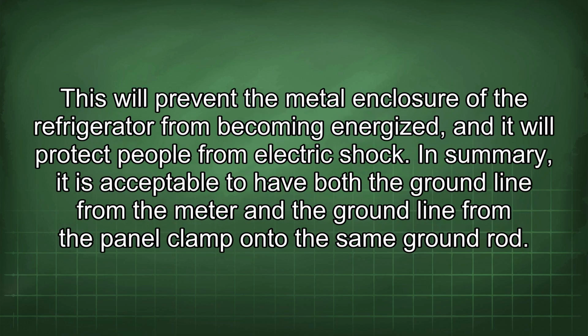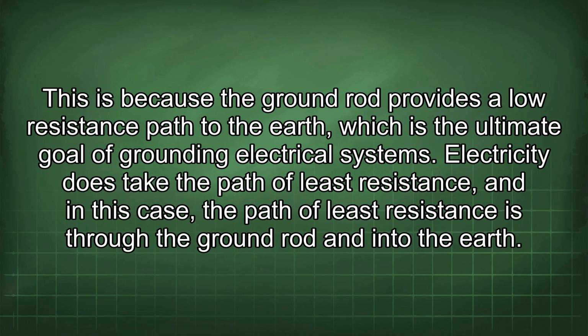This will prevent the metal enclosure of the refrigerator from becoming energized, and it will protect people from electric shock. In summary, it is acceptable to have both the ground line from the meter and the ground line from the panel clamp onto the same ground rod. This is because the ground rod provides a low resistance path to the earth, which is the ultimate goal of grounding electrical systems. Electricity does take the path of least resistance, and in this case, the path of least resistance is through the ground rod and into the earth.